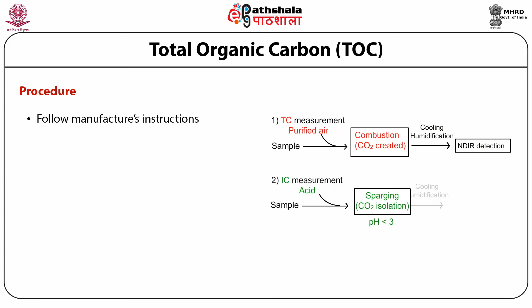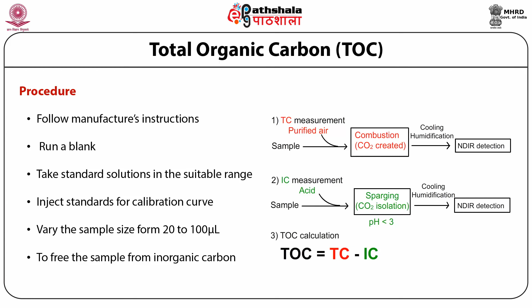For TOC determination, we have to follow the manufacturer's instructions for analyzer assembly, testing, calibration and operation. First of all, we have to run a blank in the system. Then the latest instruments provide the direct value of TC, that is total carbon, and IC, that is inorganic carbon, in milligram per liter. For that, we take the standard solution in a suitable range, then inject the standard to prepare the calibration curve, then vary the sample size from 20 to 100 microliter, and free the sample from inorganic carbon. Take the sample by a capillary syringe and inject it into the analyzer.